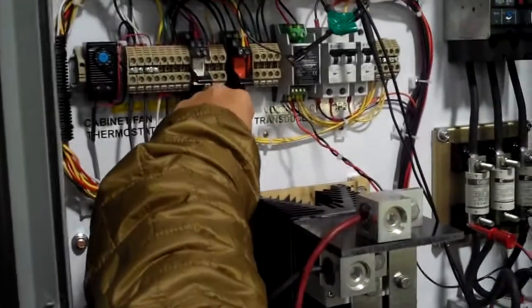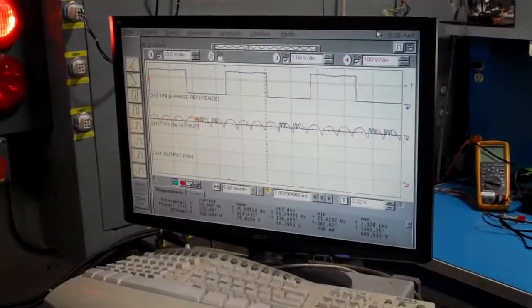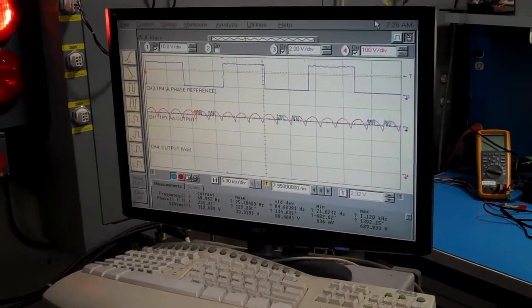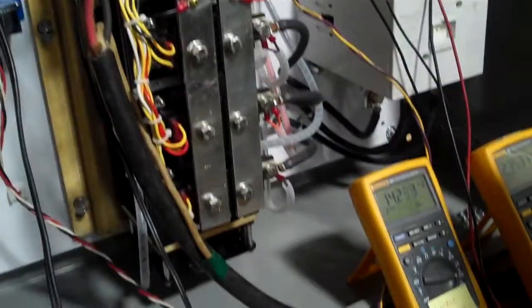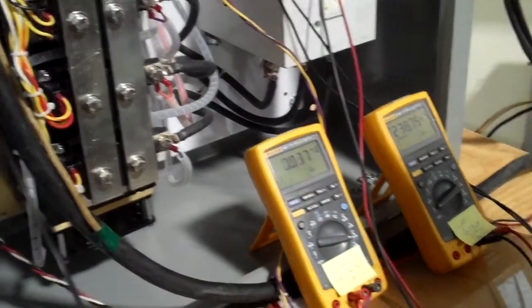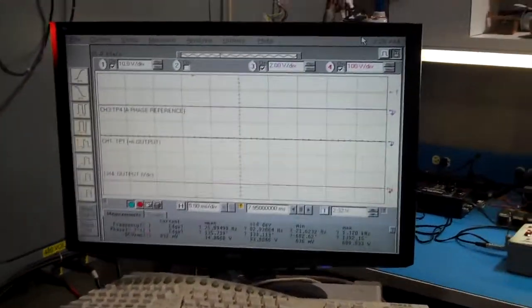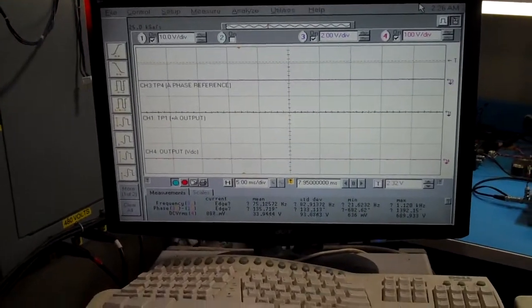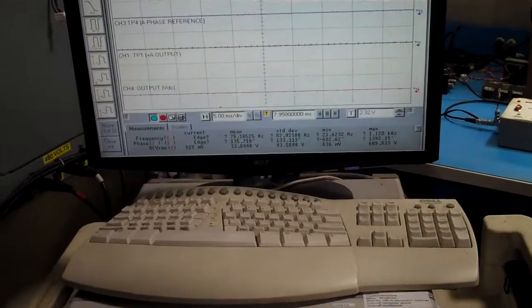So if I now bring in my emergency stop, I can see right there, it completely stopped, it inhibited. If I bring it back again, it's there. So I'm going to remove the 120 again from the contactor, and I'm going to go ahead and bring that 120 again, and we'll see how the output across the load will soft start. Here we go.